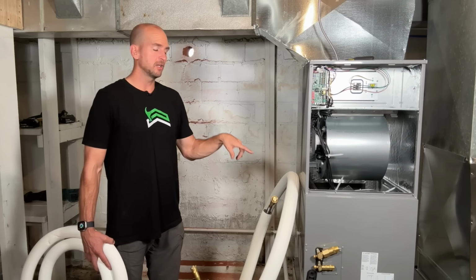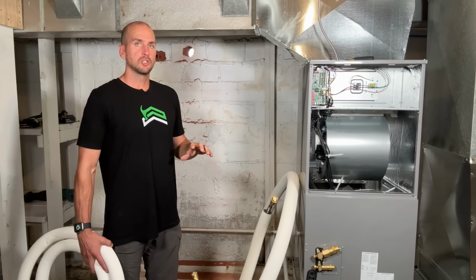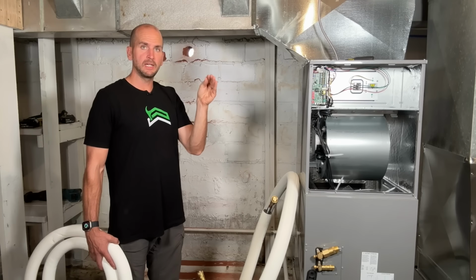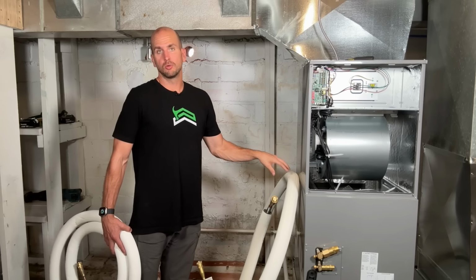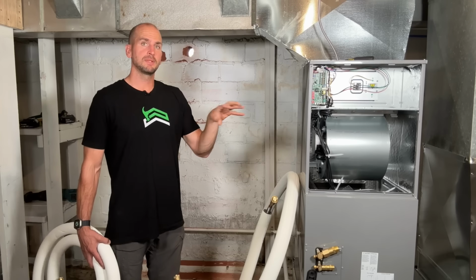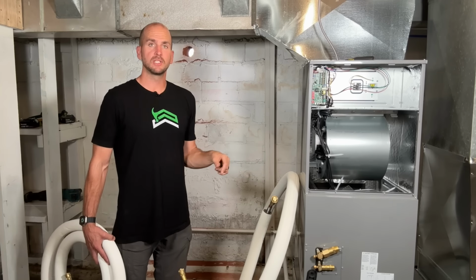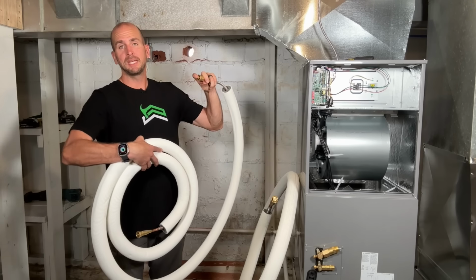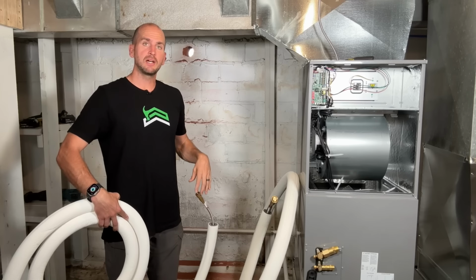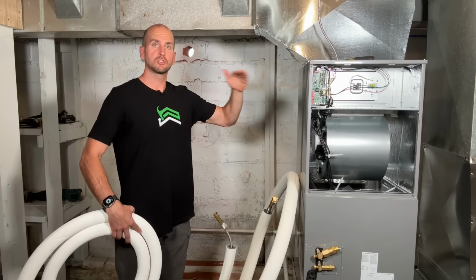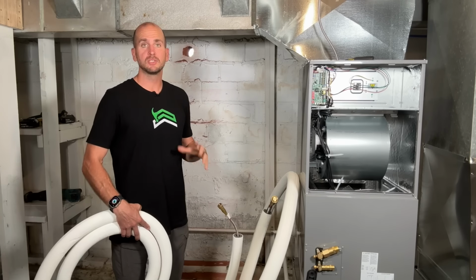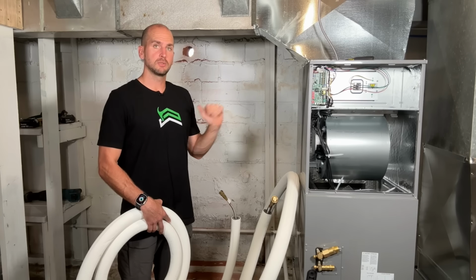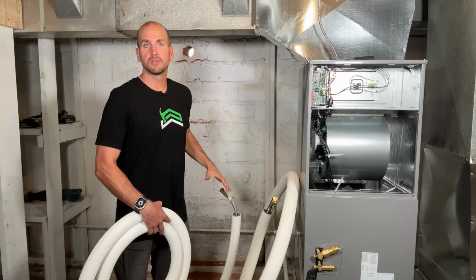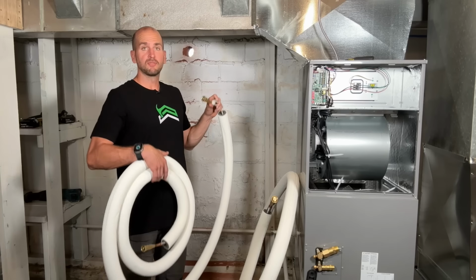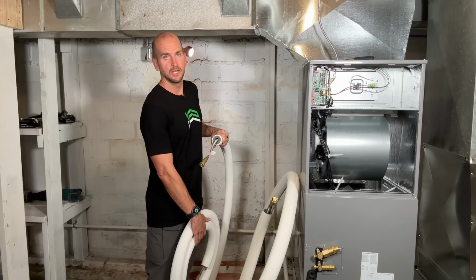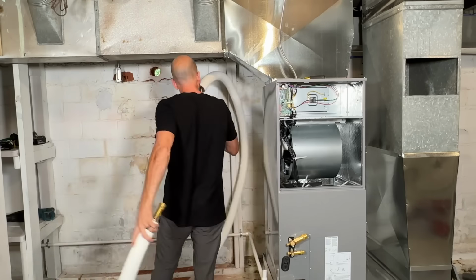Take your time. Do not overbend these lines. You shouldn't try to cut too close of a radius, because remember, these are already pressurized. That's the key to the system, and that's also why we installed those little valves there. Each of these lines has a little piston in it, and once we tighten those down, that piston is gonna depress, and that's gonna pressurize the system. Then we're gonna open up the valves, and that should mean our system is ready to go, and then we can start powering things up and getting our thermostat connected. But first up, let's go ahead and route these lines.